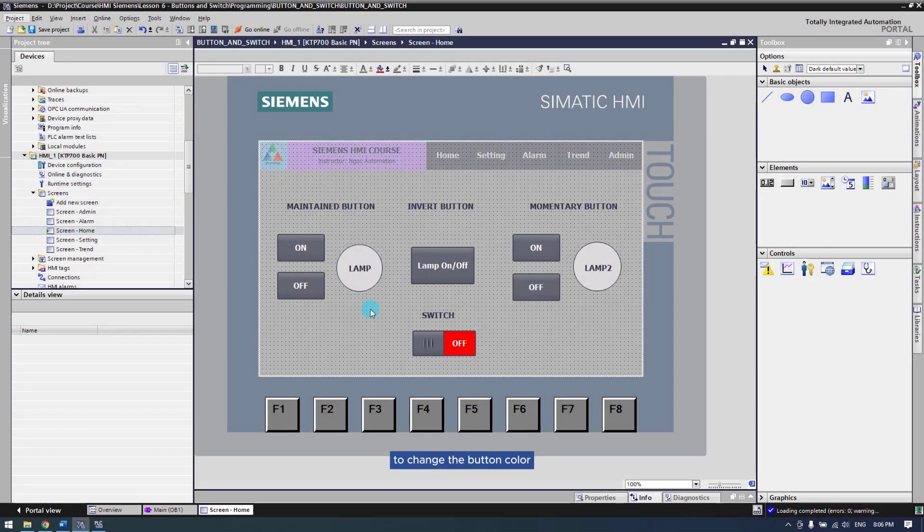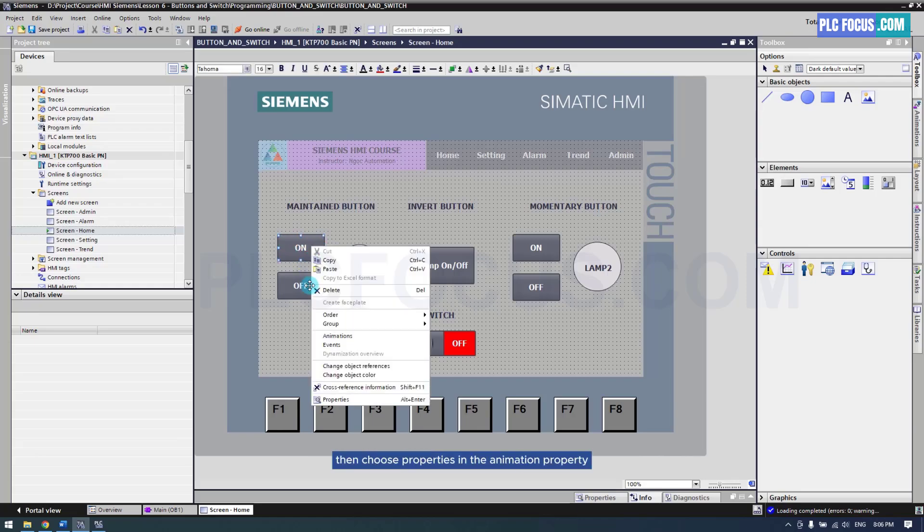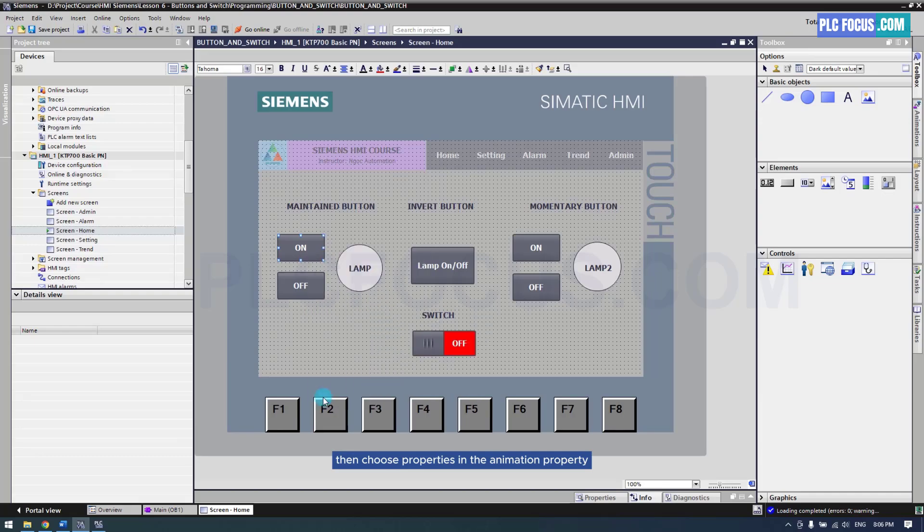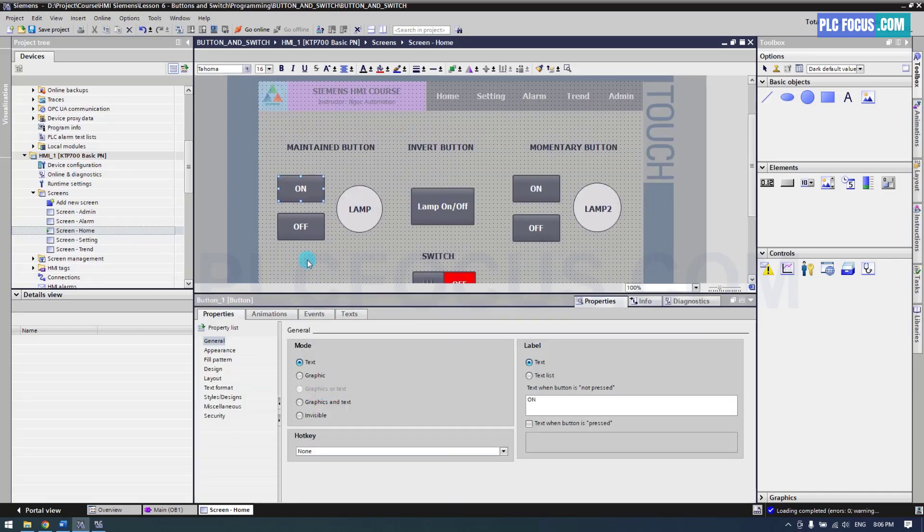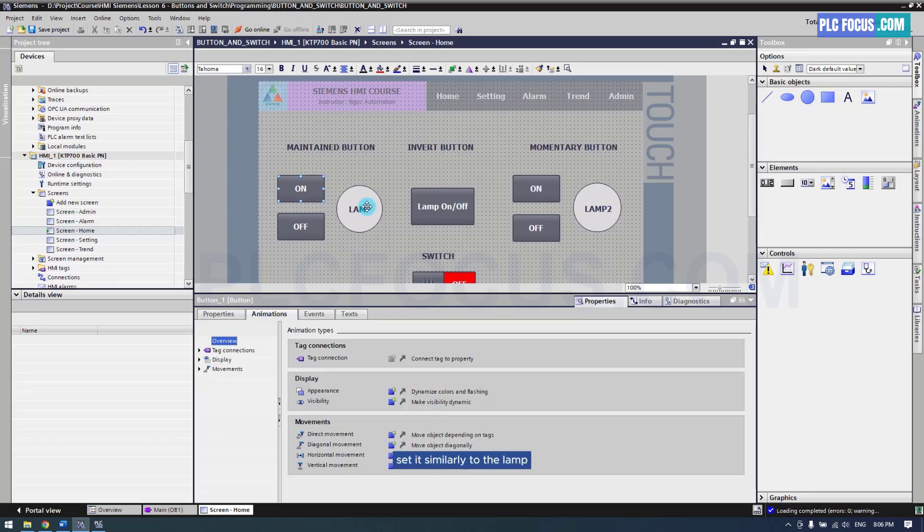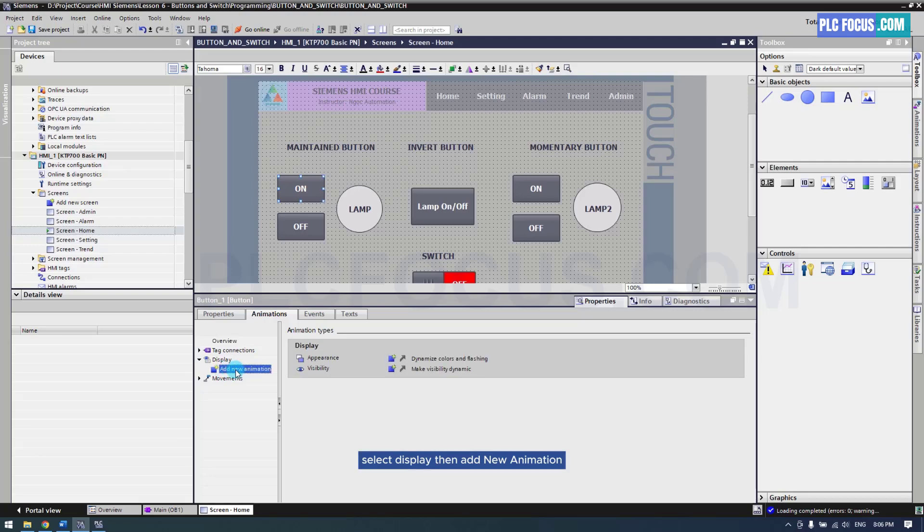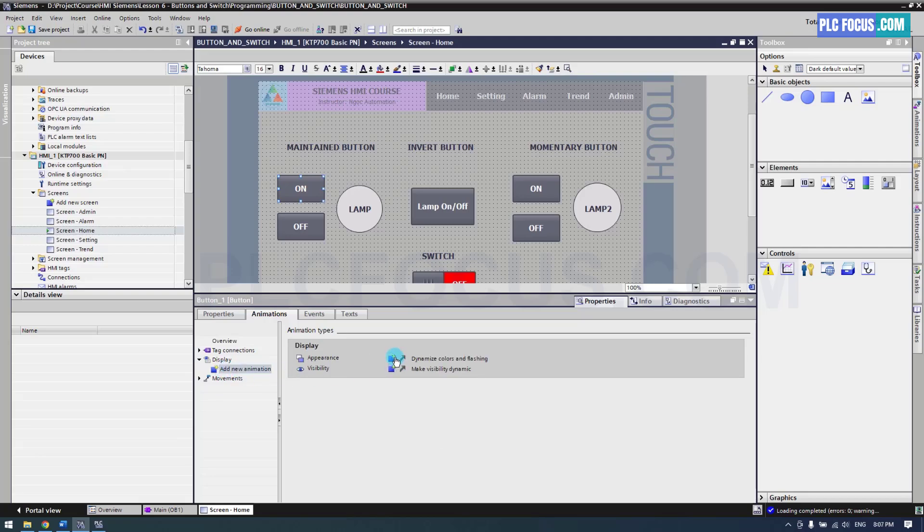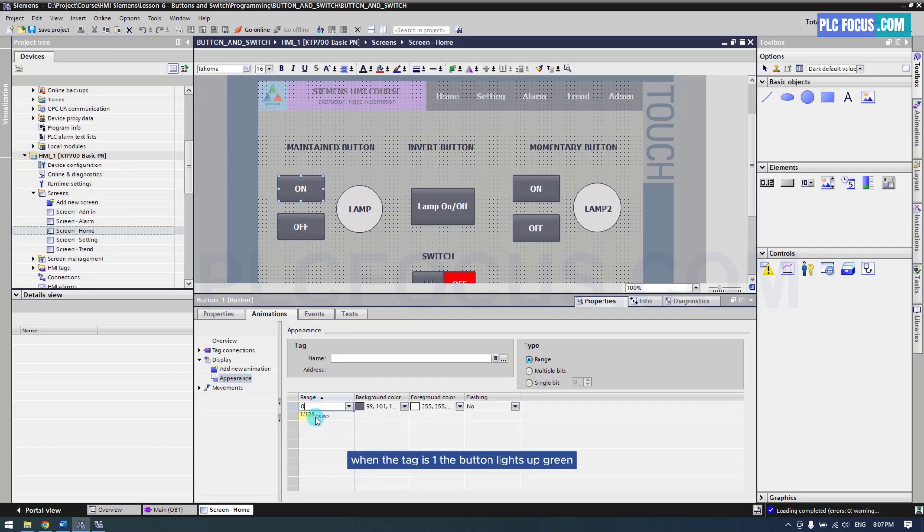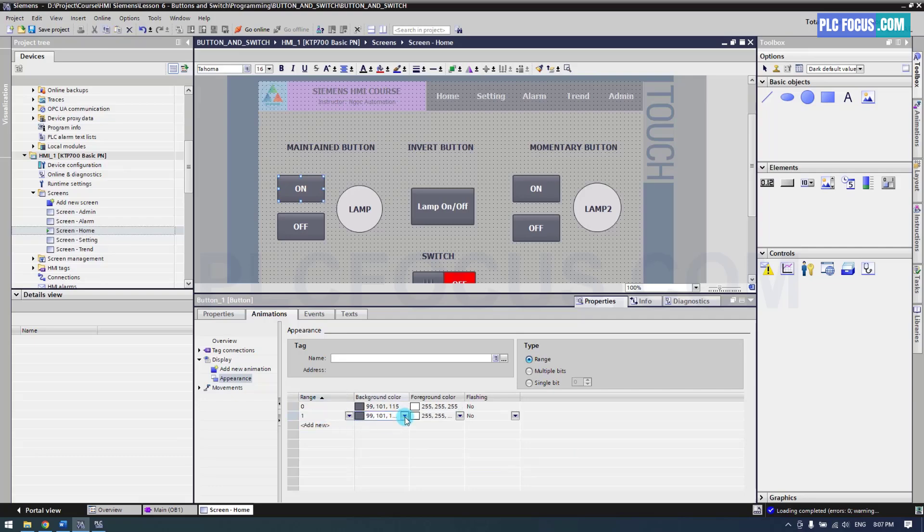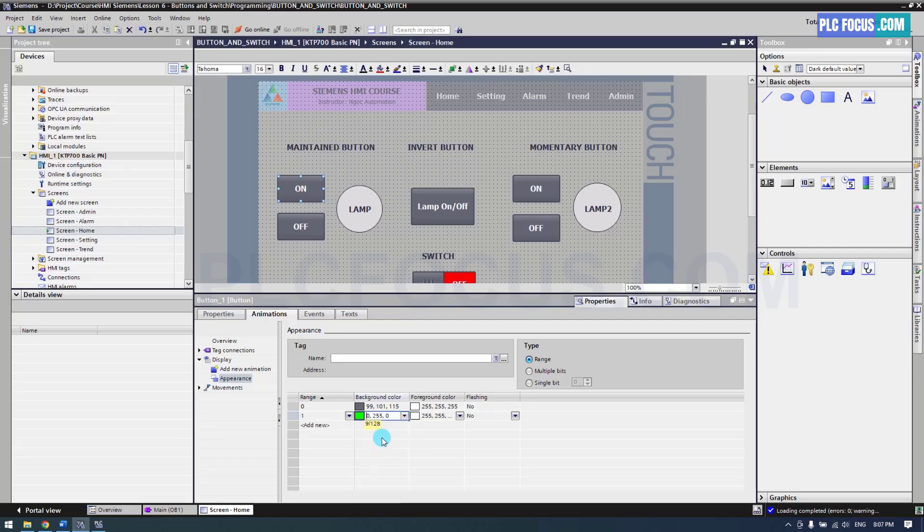To change the button color, for example you want the on button to be green when the light is on, right-click the button then choose properties. In the animation property, set it similarly to the lamp. Select display, then add new animation to add the property. When the tag is 0 it displays the default color. When the tag is 1 the button lights up green. The tag is the lamp tag. Select folder tag, then click on the button and drag the lamp tag to the location.